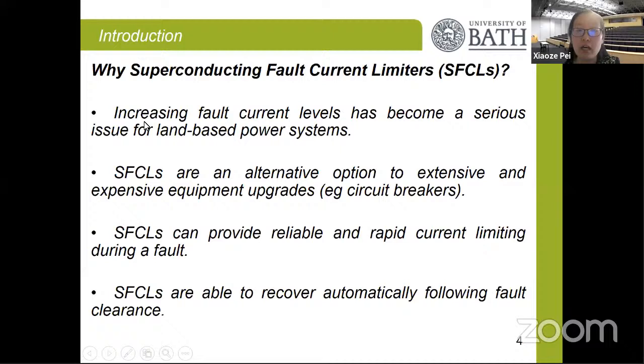So which means there is an increase in the fault current levels. And this has been a serious problem for the land-based power system, because when the power system was initially designed, all the circuit breakers and the protection units were designed based on the maximum capability at the time of designing. And because this is a developing area, with the increase of load and the increase of generation, the fault current levels keep increasing. And a lot of the fault current levels are already approaching the maximum that the circuit breaker is able to handle. So what are the options?